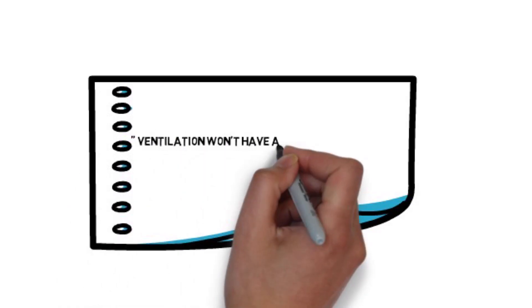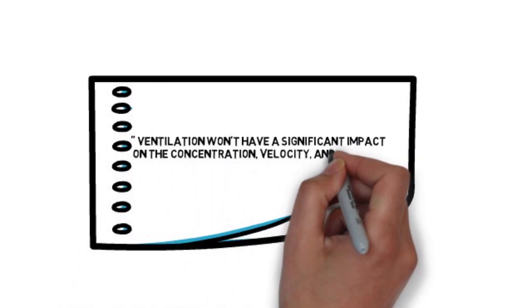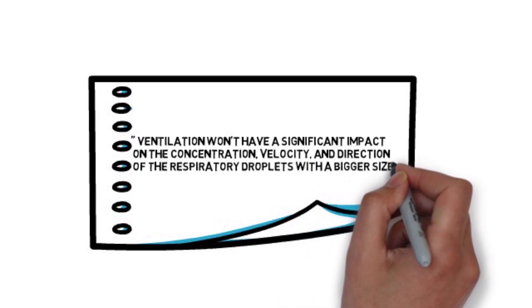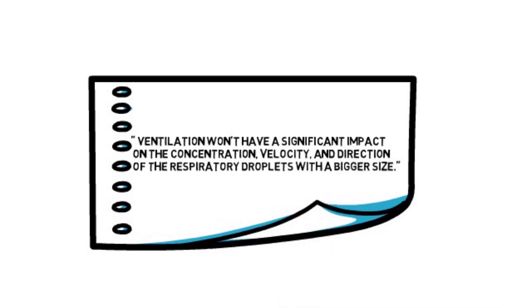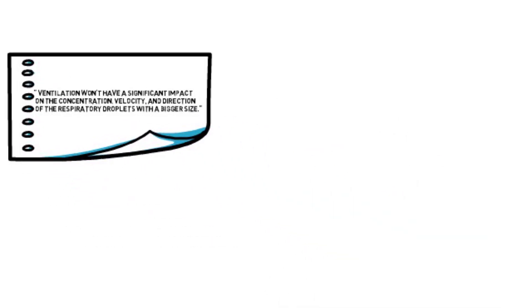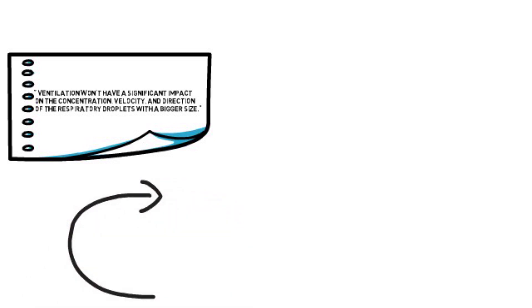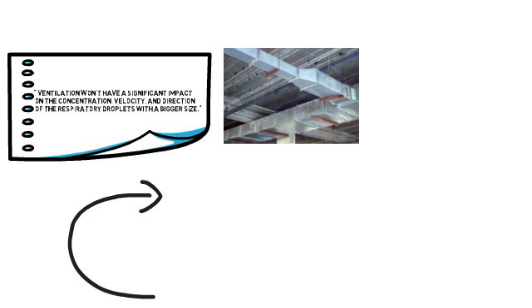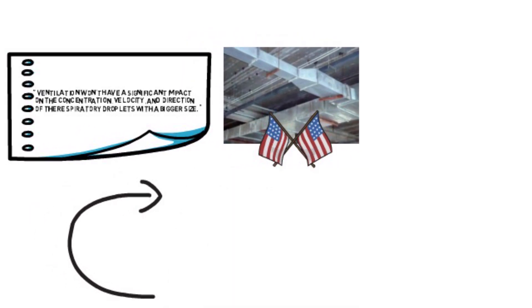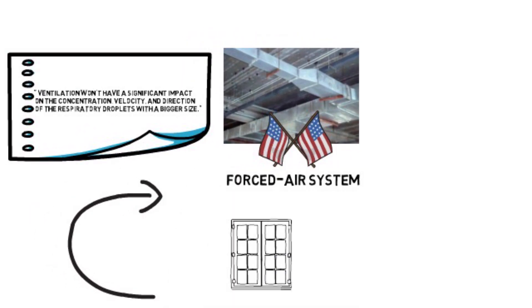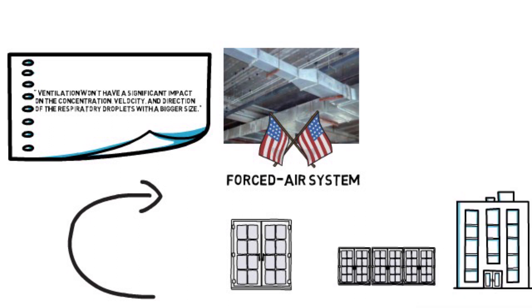Based on this ASHRAE document, ventilation won't have a significant impact on the concentration, velocity, and direction of the respiratory droplets with a bigger size. However, aerosols can travel a relatively long distance through air ducts in the buildings. Because most HVAC systems in the U.S. are forced air systems, the virus could be transmitted through HVAC ducts to the same floor or even the entire building.